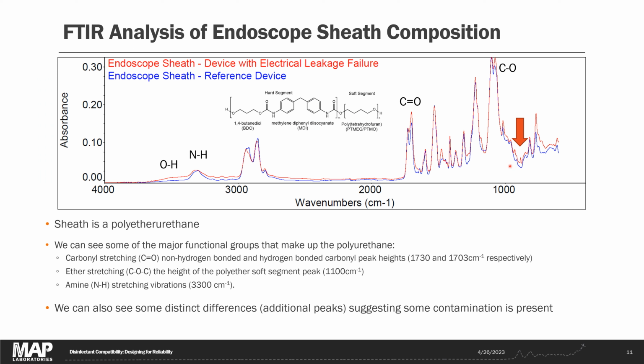Here I've shown the infrared absorption spectrum for the failed device in red, and for that same endoscope sheath material on a reference device in blue. We can see some peak structures that are typical of polyether urethanes. We have the ether group CO stretching here. We have carbonyl from the urethane linkage here at 1700-ish. We have NH stretching and OH stretching, so all very typical things of a polyurethane.